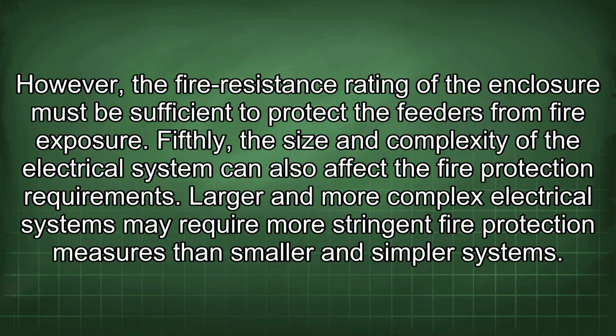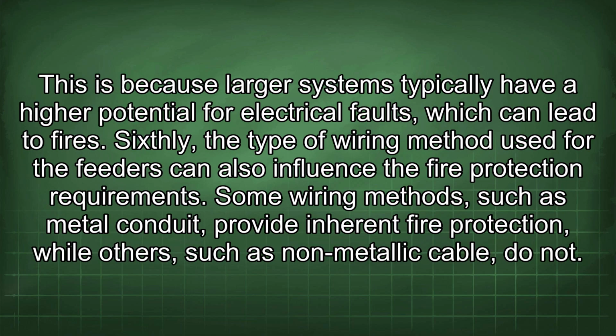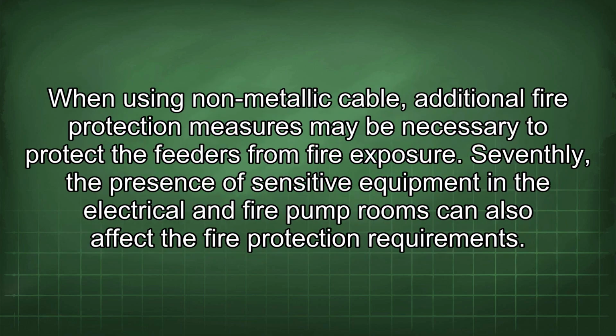Fifthly, the size and complexity of the electrical system can also affect the fire protection requirements. Larger and more complex electrical systems may require more stringent fire protection measures than smaller and simpler systems. This is because larger systems typically have a higher potential for electrical faults, which can lead to fires. Sixthly, the type of wiring method used for the feeders can also influence the fire protection requirements. Some wiring methods, such as metal conduit, provide inherent fire protection, while others, such as non-metallic cable, do not. When using non-metallic cable, additional fire protection measures may be necessary to protect the feeders from fire exposure.